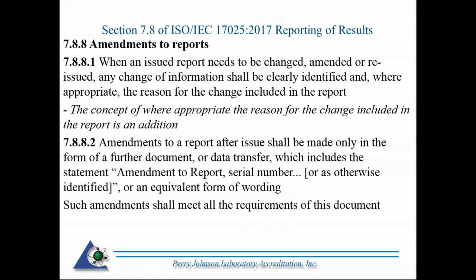Okay, section 7.8.8, that's amending reports. Perhaps you release a report and you have to add to it, or perhaps you have to issue a new report. So when an issued report needs to be changed, amended, or reissued, any change of information shall be clearly identified, and where appropriate, the reason for the change included in the report. So the concept of, where appropriate, the reason for the change, specifying why you had to make a change in the report, that is a new requirement. That was not in the 2005 standard.